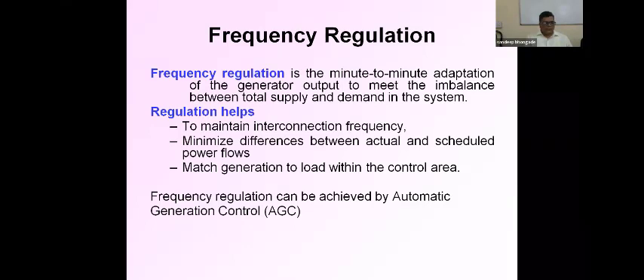Okay. Now, in doing so, regulation helps to maintain the interconnection frequency. Maintaining the interconnection frequency means the system frequency should not deviate or vary much about its nominal value. Okay. This frequency regulation also helps to minimize the differences between actual and scheduled power flow. It also helps match the generation to load within the control area. Now, this service can be provided by any appropriately equipped generator that is connected to the grid and electrically close enough to the local control area, provided no physical or economical transmission limitation prevents the transport of power.